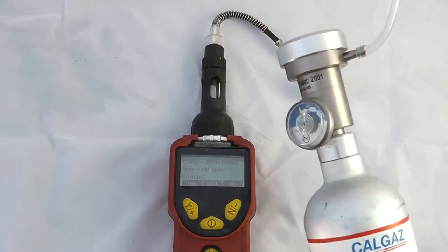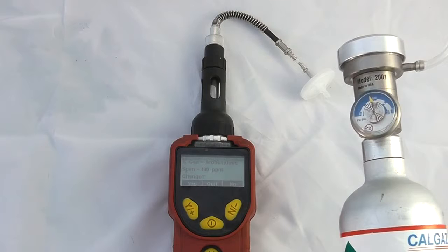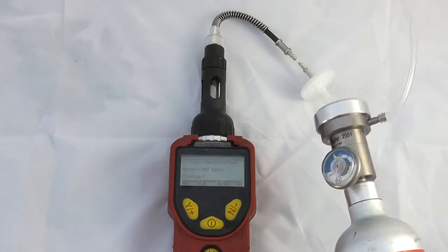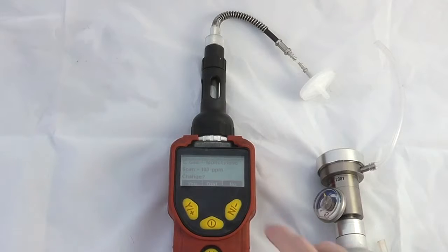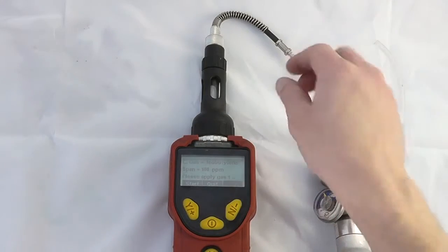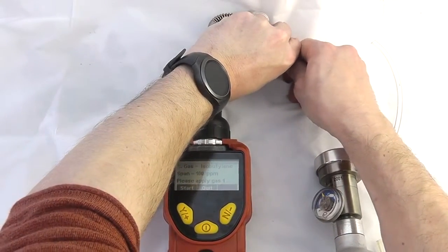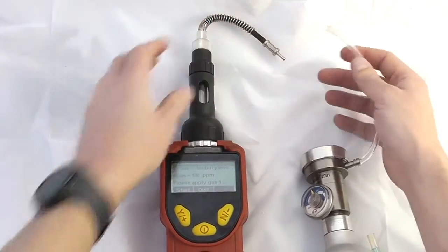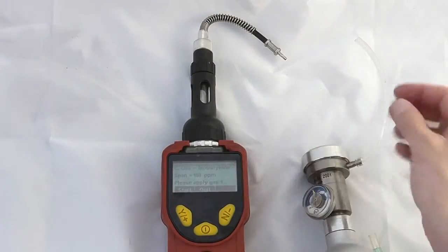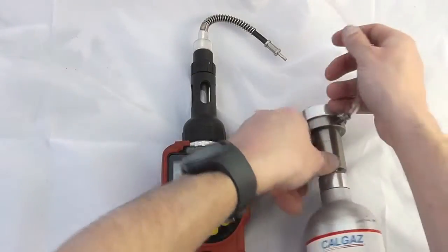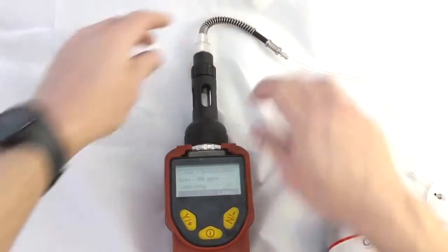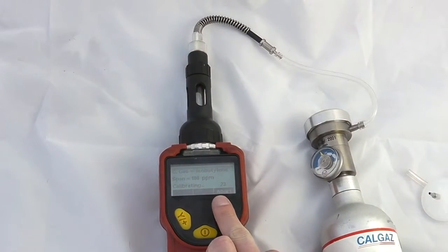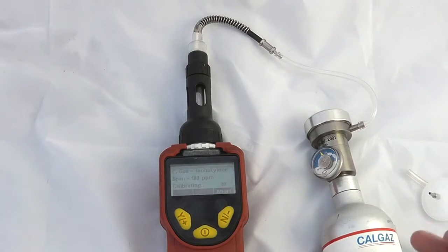I happen to have a can of isobutylene with an on-demand regulator, so I'm going to use isobutylene for my particular calibration function. We don't want to change any of the values here, so we'll say no, and then it'll ask us to apply gas 1, so removing the hydrophobic filter from the top of the instrument. Because I'm using an on-demand regulator, the instrument will automatically apply gas as soon as I've enabled it. So we'll put the gas on the end of the instrument and it will immediately start a gas flow. The instrument recognises it's seen gas and is now doing the 30-second countdown on the calibration factor. You could use a manual flow regulator as well as a different option.